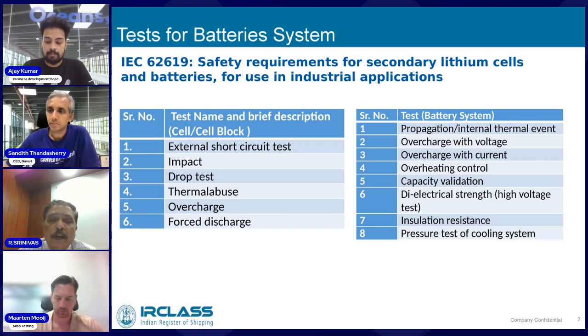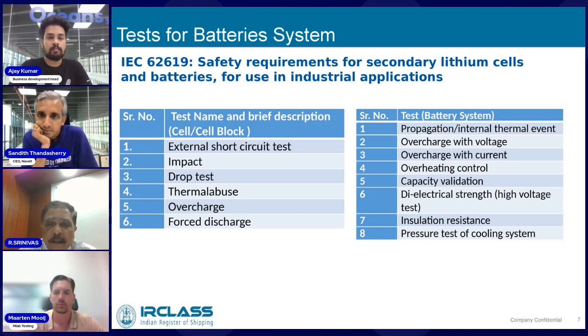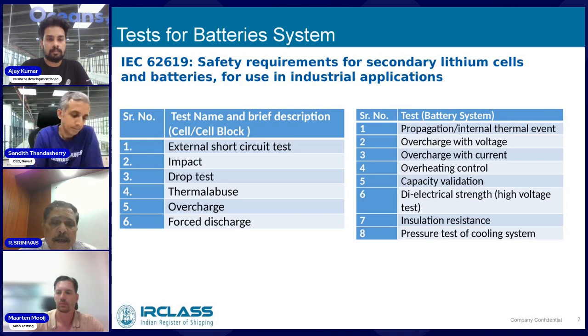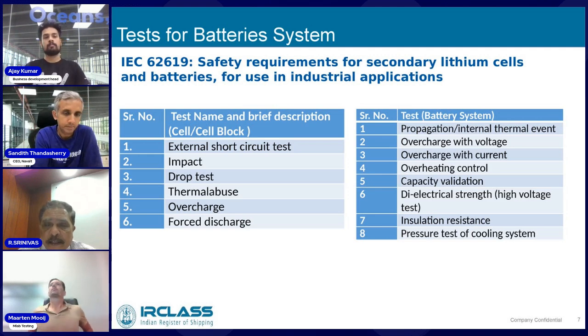One of the important tests is propagation - that is, in case there's a short, we physically try to create a thermal runaway. In case of an internal short, it's tested at the cell level, and at the block level we have to see that it doesn't propagate to the adjacent cell.